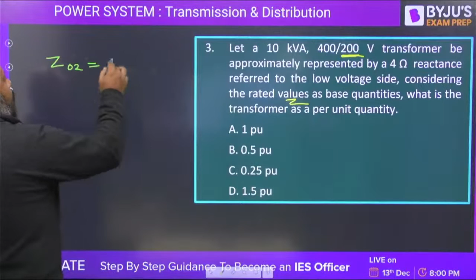You need to find the secondary side, low voltage side base impedance. Then you can easily find the per unit impedance. The secondary side base impedance is going to be voltage square, that is 200 into 200, divided by complex power, that is not square, simply complex power, 10 into 10 to the power 3. If you simplify this, you will get this also as 4 ohms. Then what is going to be the per unit impedance? It is going to be 4 upon 4, that is 1 per unit. So what is the correct answer? A.